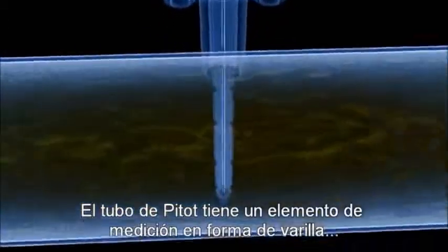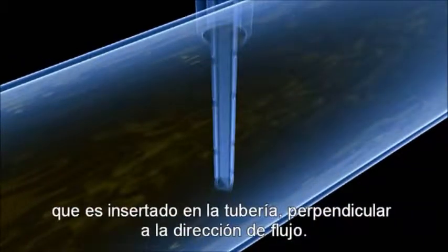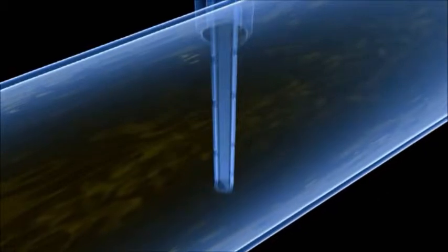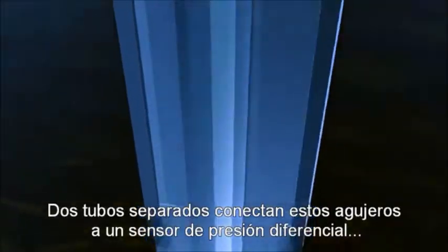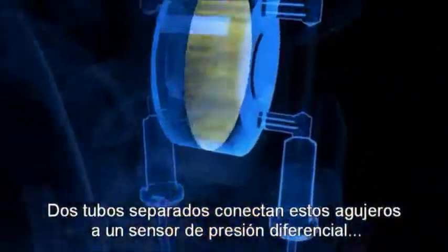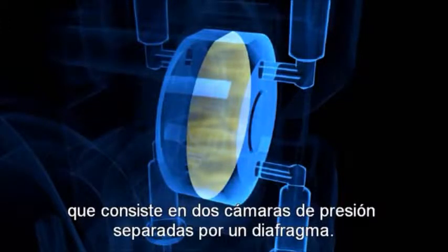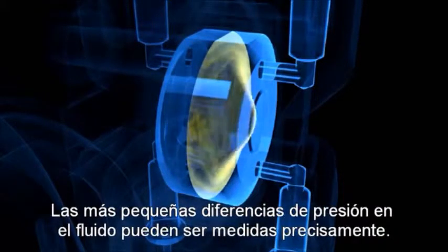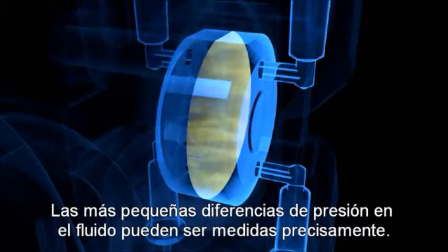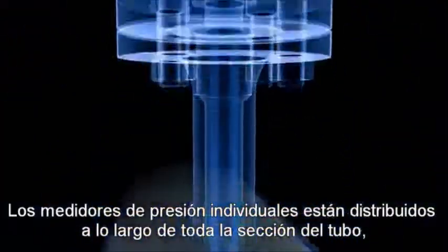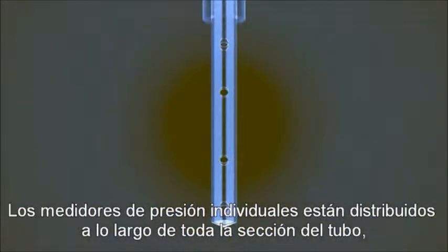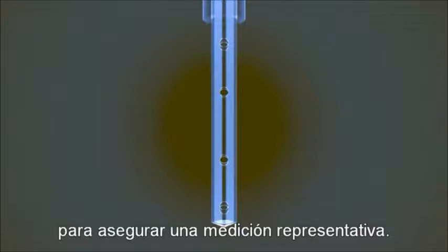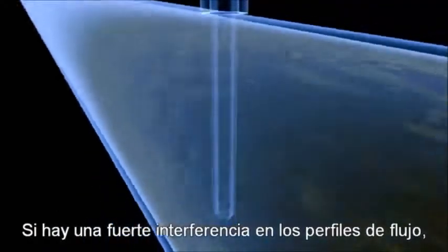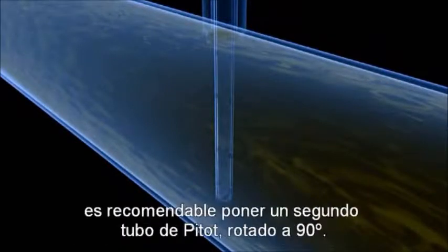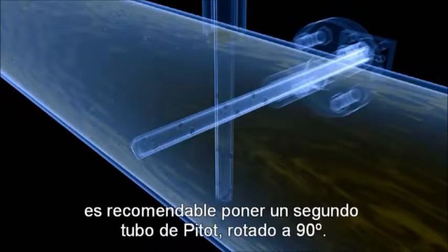Pitot tubes have a rod-shaped measuring element that is inserted into the pipeline perpendicular to the flow direction. On the front and rear of this probe are several holes. Two separate tubes connect these holes to a differential pressure sensor. With its two pressure chambers, separated by a diaphragm, the tiniest pressure differences in the flowing fluid can be precisely measured. The individual pressure taps are distributed along the entire pipe cross-section to ensure a representative measurement. If there is strong interference in the flow profiles, it's advisable to fit a second Pitot tube, rotated by 90 degrees.